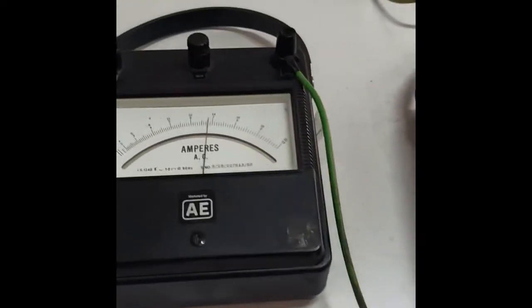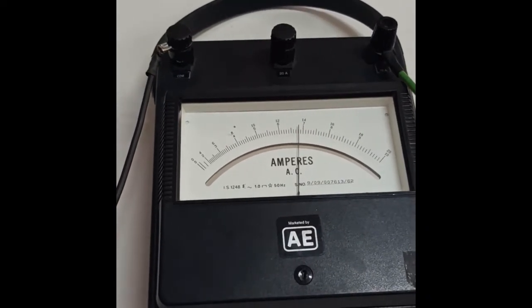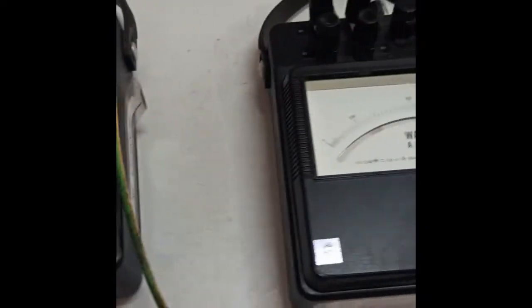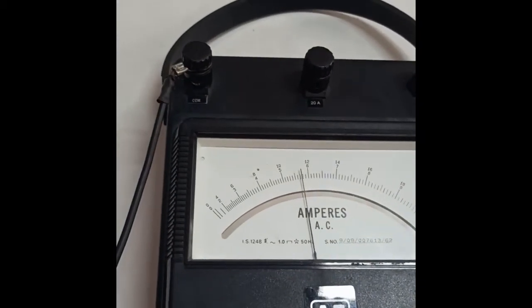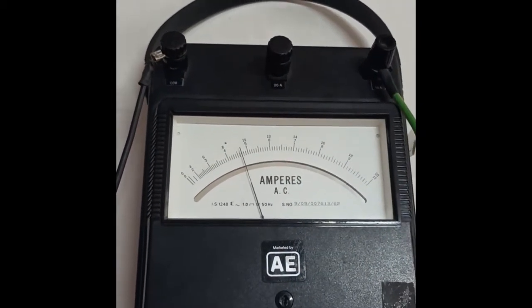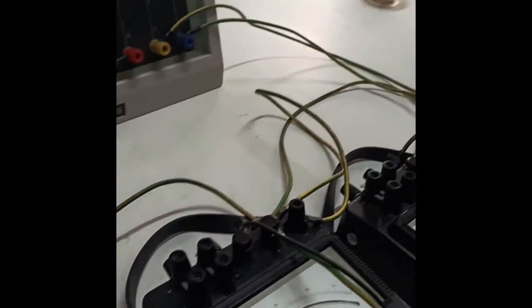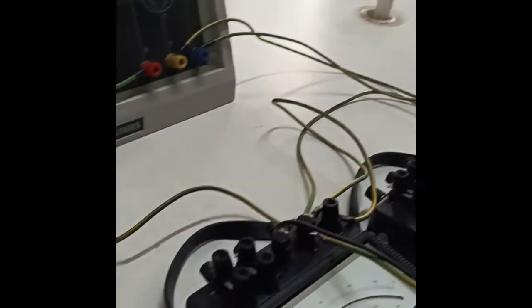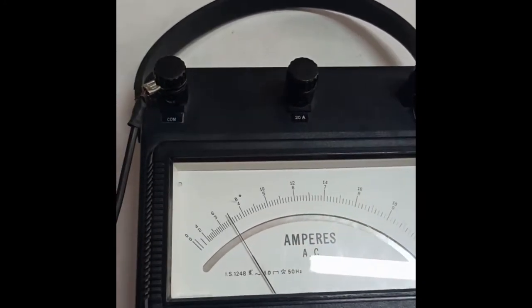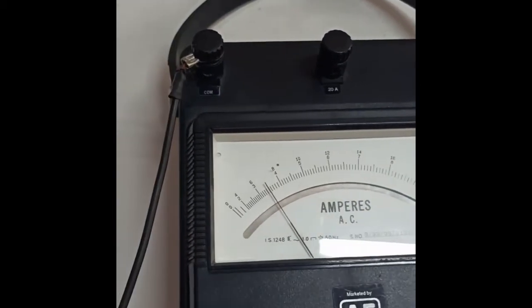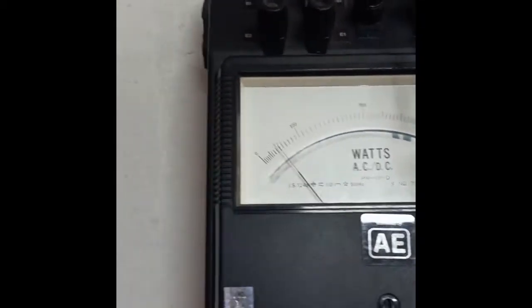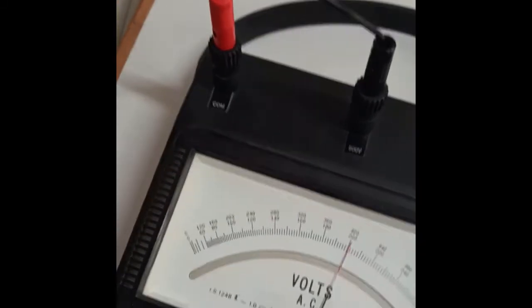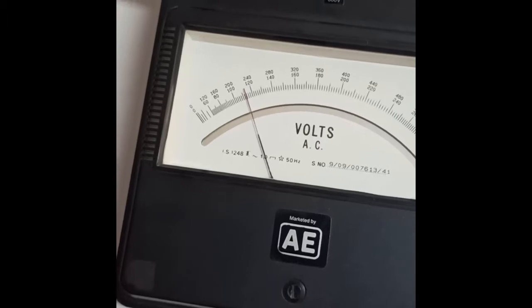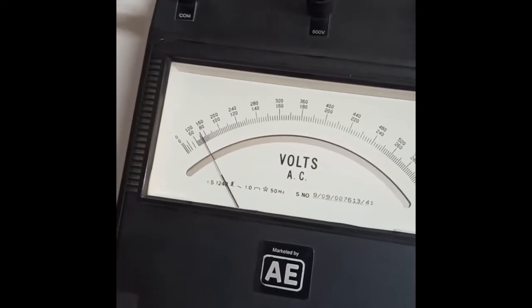Once the rated current, that is 7 amperes in the ammeter, is reached, we have to reduce the load and bring it back to no load condition. We have to bring the machine back to the no load condition, that is the initial position where the current was 3.5 amperes. So reduce the load and bring it to no load condition. Then reduce the voltage to 0 and switch off the supply.